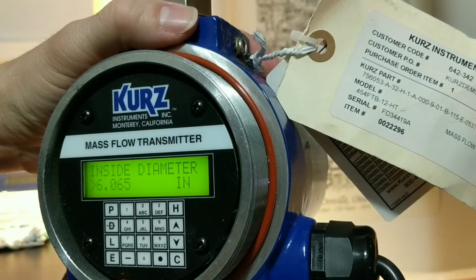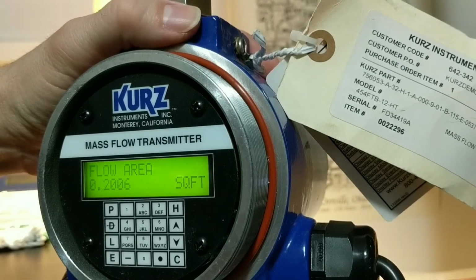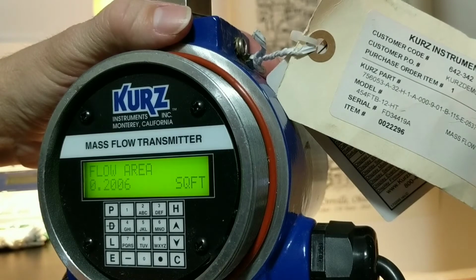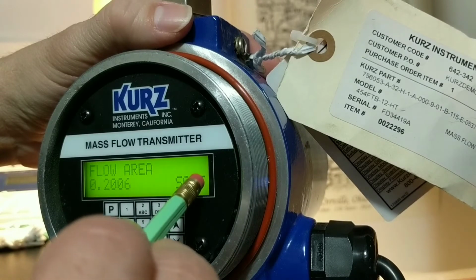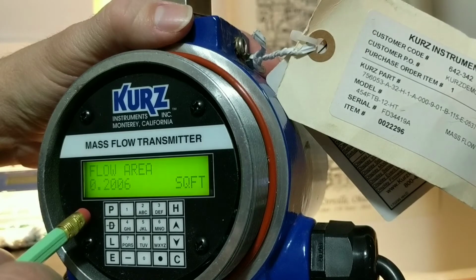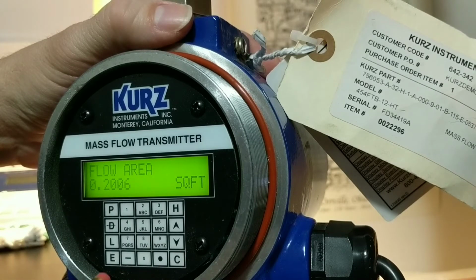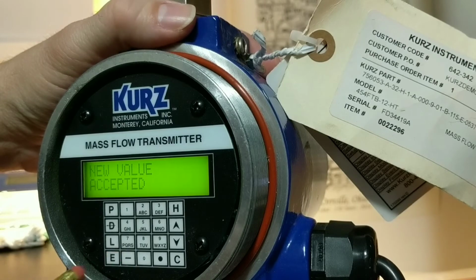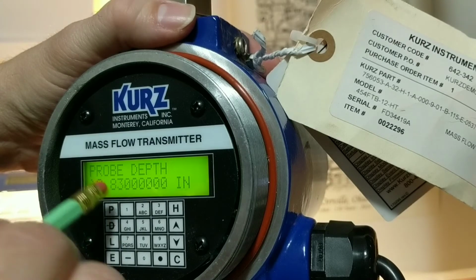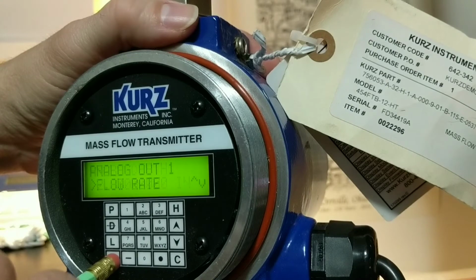6.065 inches, enter. Then the flow area, basically a different way of stating the inside diameter as well. So the entire flow area of a Schedule 40 6-inch pipe is 0.2006 square feet. And we're already set properly here, so you don't need to clear it and go into it. But I think you may have to change that on yours. Not 100% sure. We'll scroll down. The probe depth, we're not going to mess with that right now.